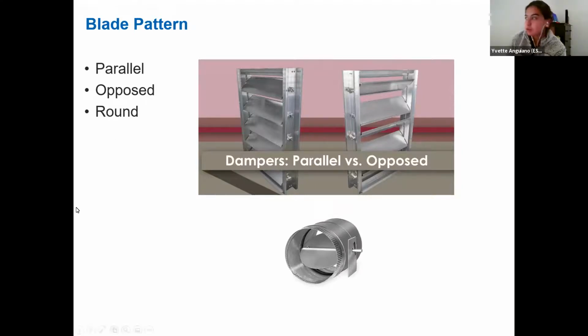For parallel blades, when you first open them, they have a very steep, more aggressive flow rate to damper position curve. So there's a significant change in the flow rate when you're going from a closed to open position. And thus those would be best used for a two-position isolation damper application. And then lastly, you've got your round dampers, which you'll use to control CFM. And typically you see those in terminal unit applications such as VAVs.